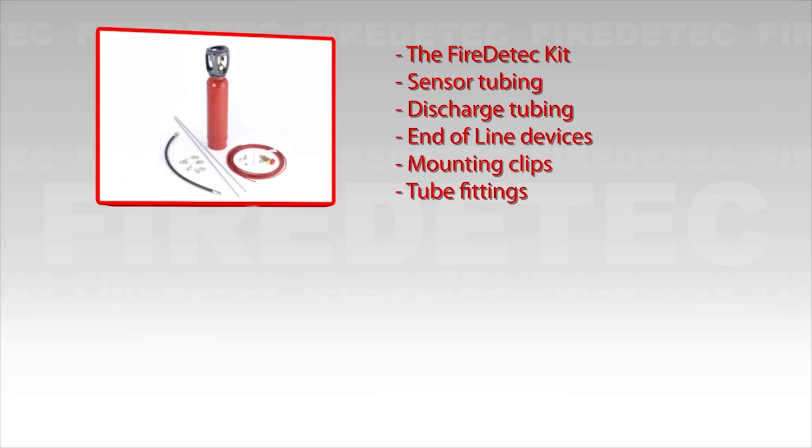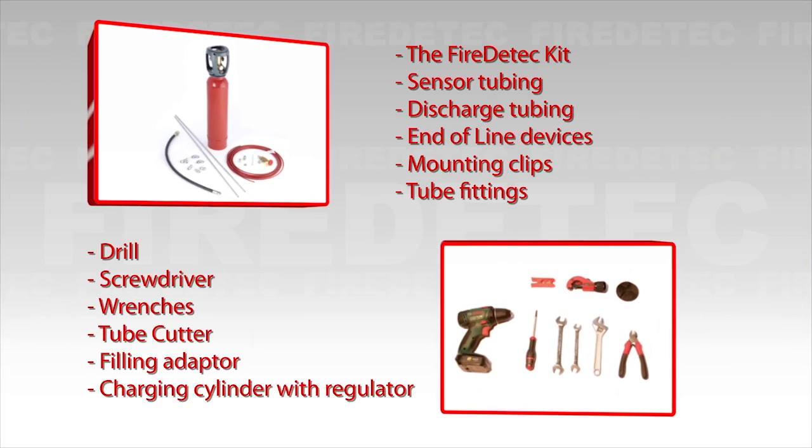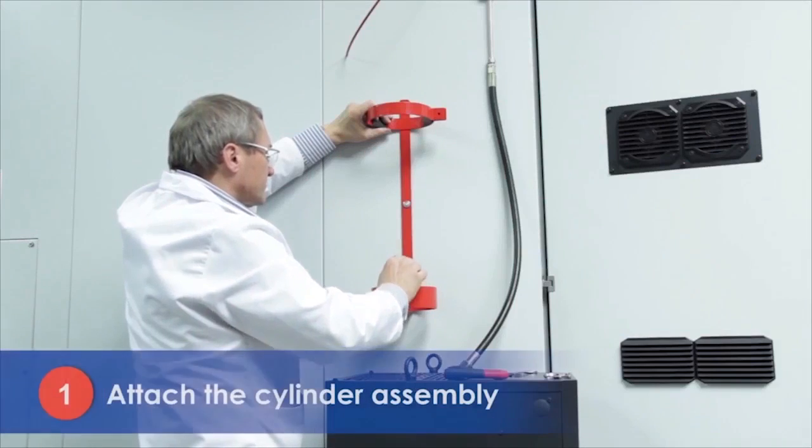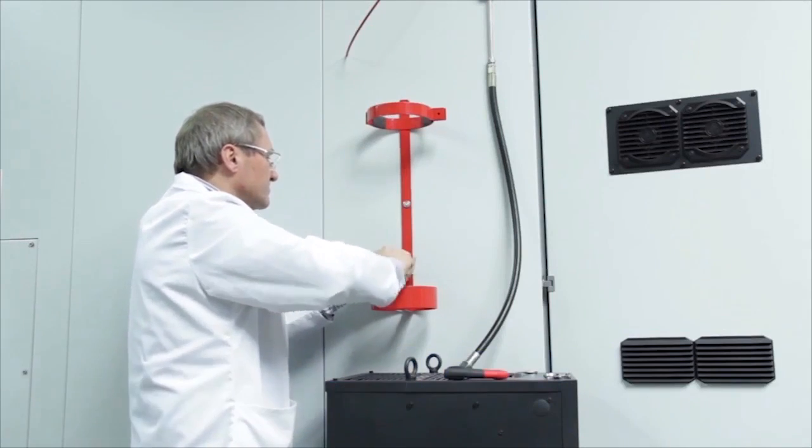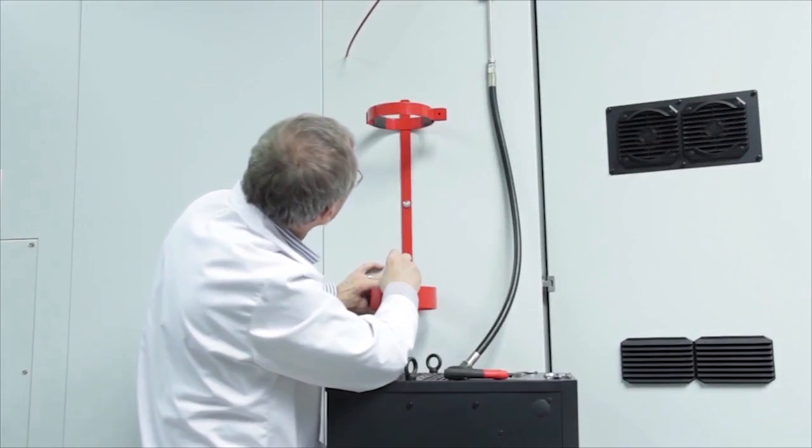Make sure you have the necessary tools for the installation, and be sure to turn off any electricity before you start. Begin by mounting the cylinder bracket between hip and eye level on either side of the electrical cabinet or on an immediately adjacent wall. Be sure the wall or panel is capable of holding at least 20 kilograms of weight.